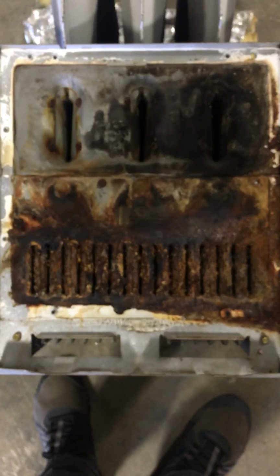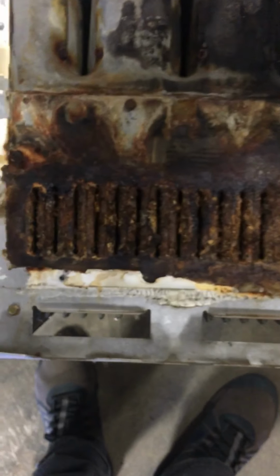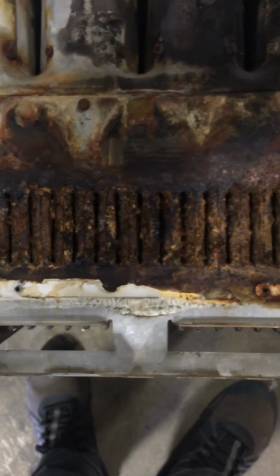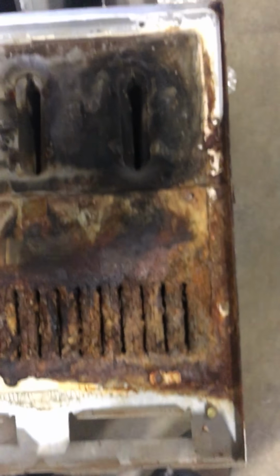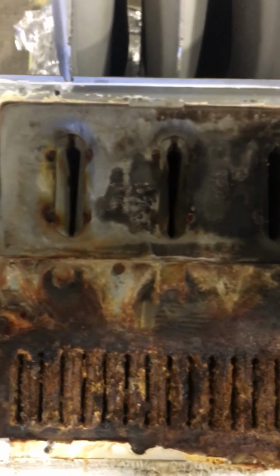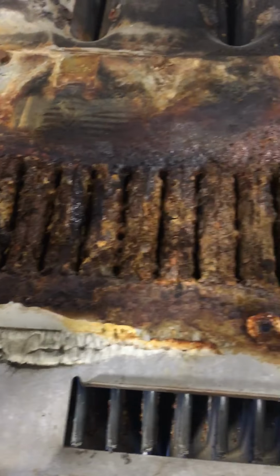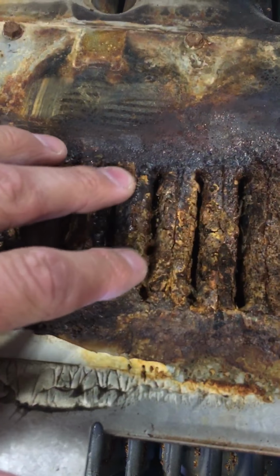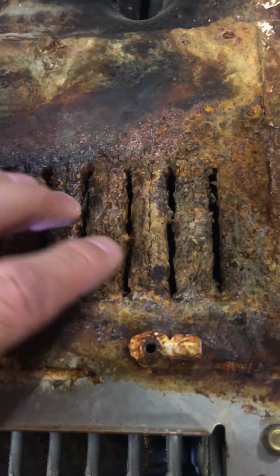Focus here. So this is the inside of the heat exchanger. You can see that is not good at all. So that is what's happening when you have a secondary heat exchanger fail. This one was actually shutting off because it was getting too hot, because you can obviously see there's no way to get any kind of air through there, airflow, or get your flame through there at all.